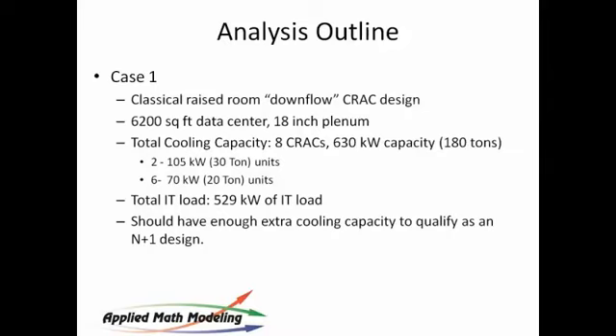So let's take a look at the first case. Here we have a classical room. It's a downflow design. I mentioned this before. It's about 6,000 square feet, 18-inch plenum. You may recognize this design because it's been used a lot over the years. Its total capacity here, 8 CRAC, 630 kW, 180 tons.